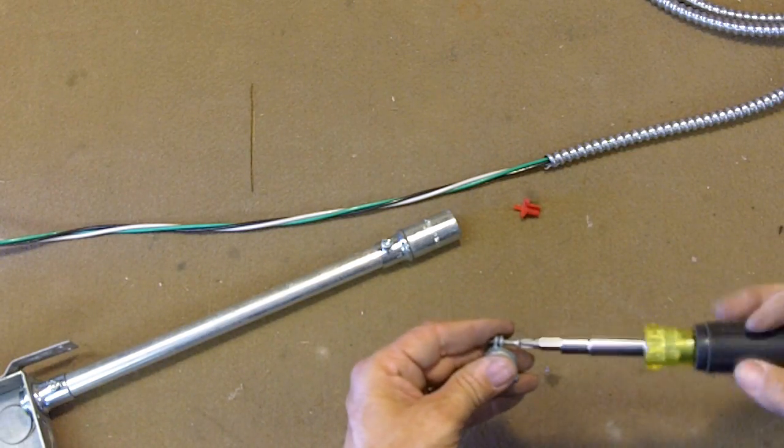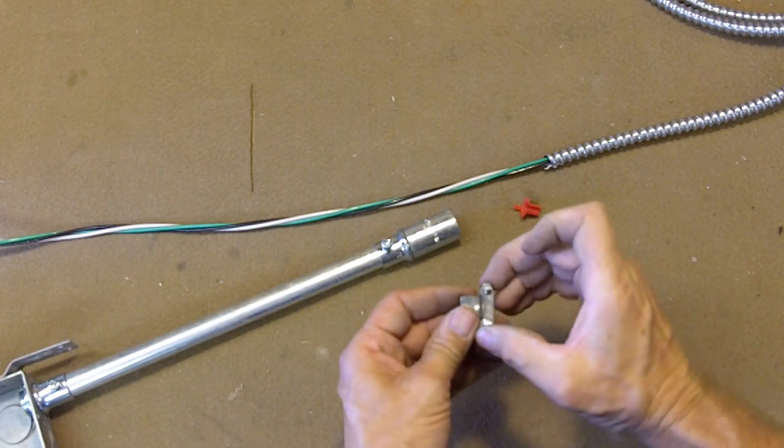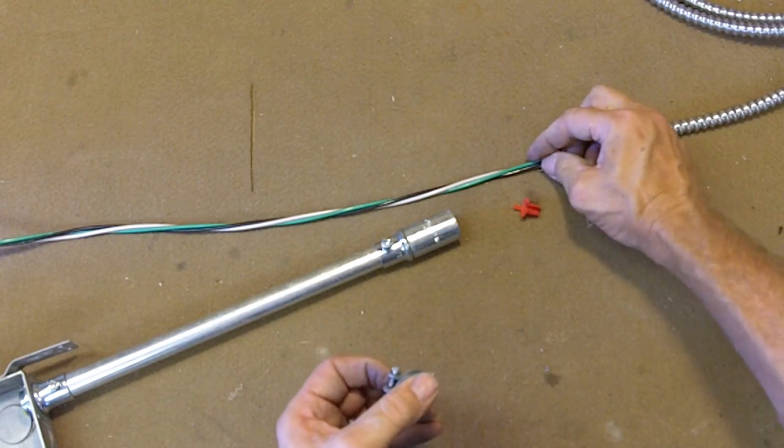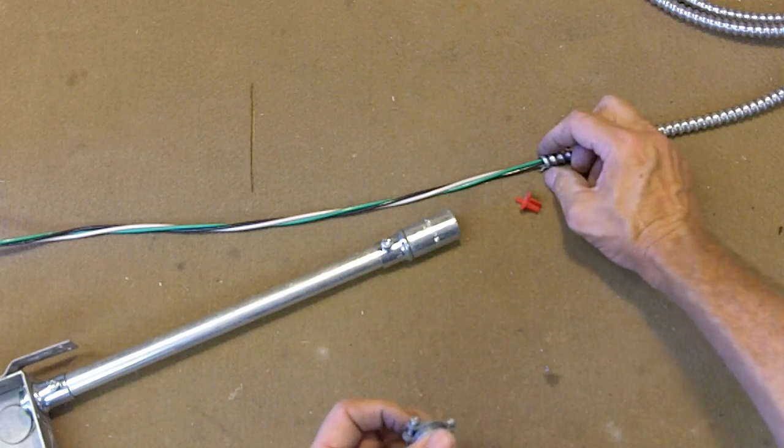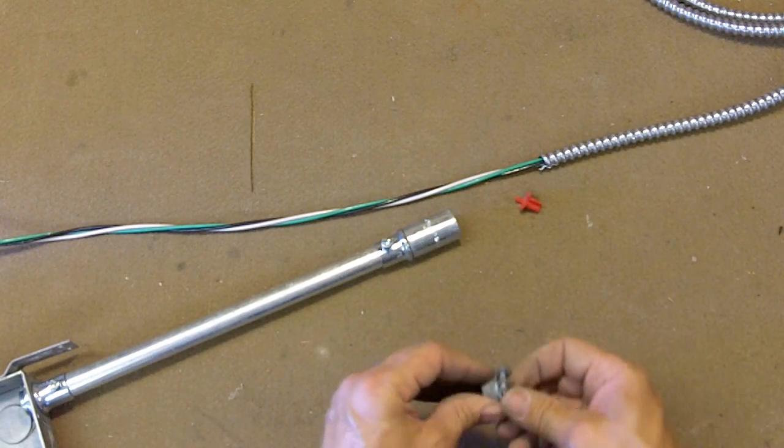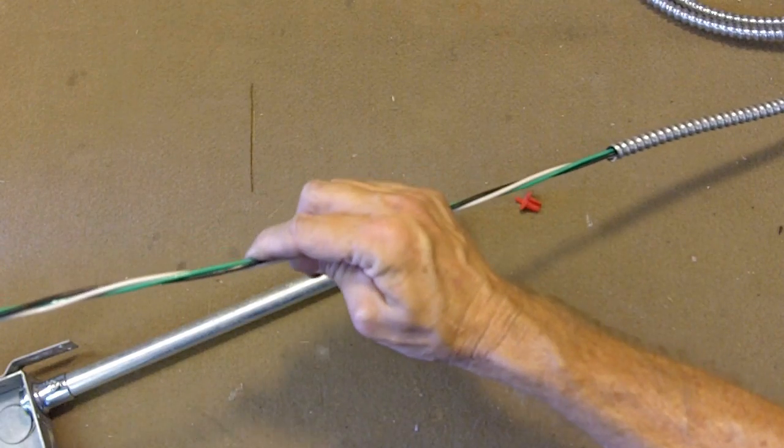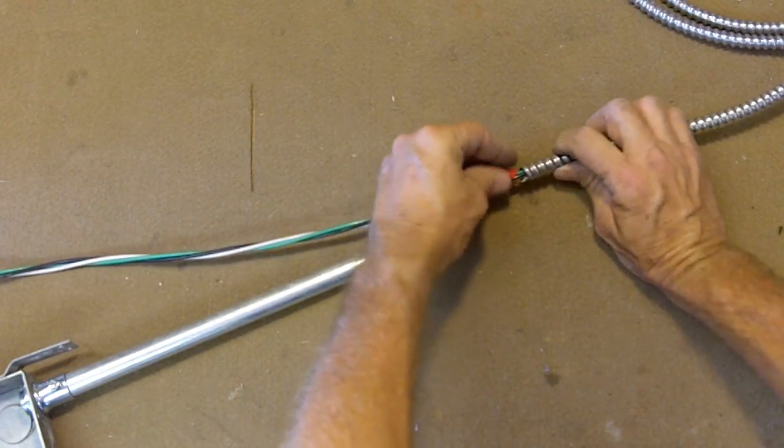I know a lot of people use drills on these. I don't recommend it mainly because when you go to tighten these down, you can crimp these wires so bad that they'll end up short inside the wire. Even with an anti-short, I've seen them where they trip out.